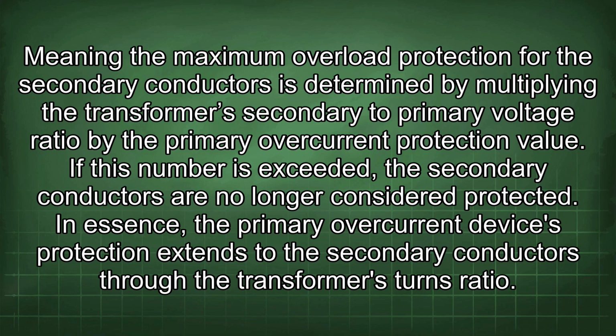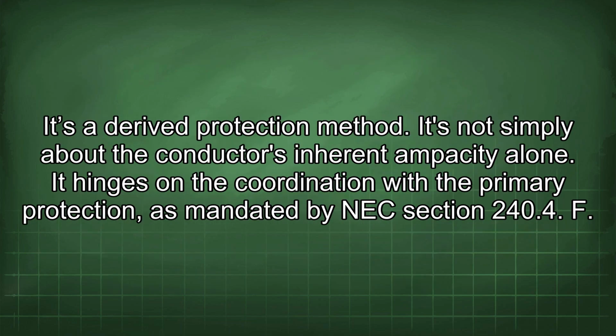In essence, the primary overcurrent device's protection extends to the secondary conductors through the transformer's turns ratio. It's a derived protection method. It's not simply about the conductor's inherent ampacity alone. It hinges on the coordination with the primary protection as mandated by NEC section 240.4(F).